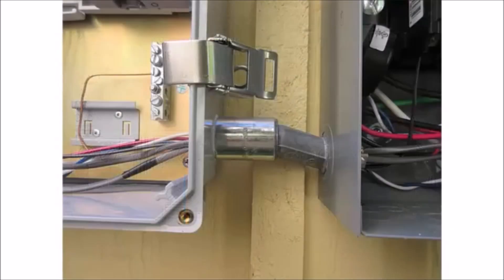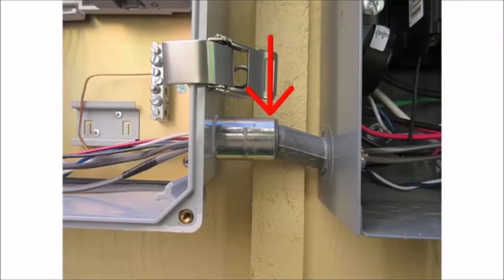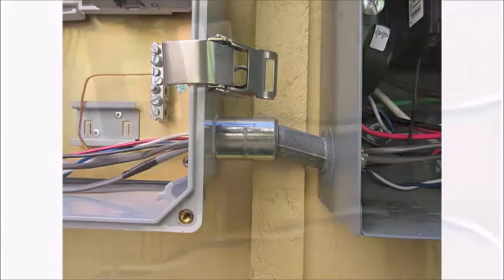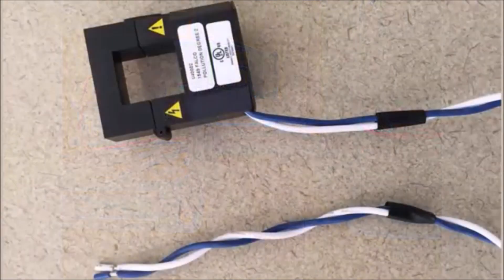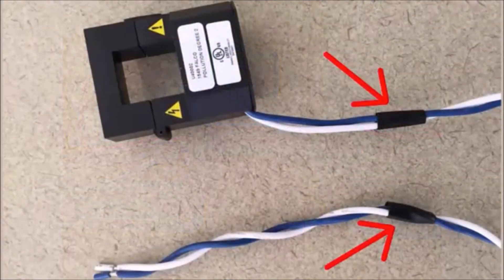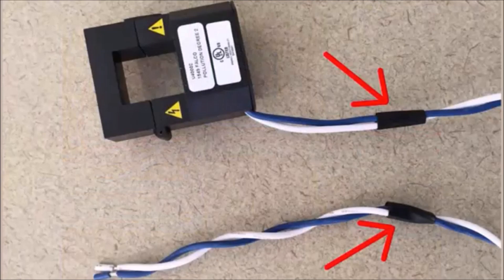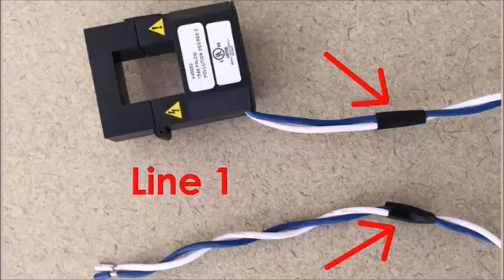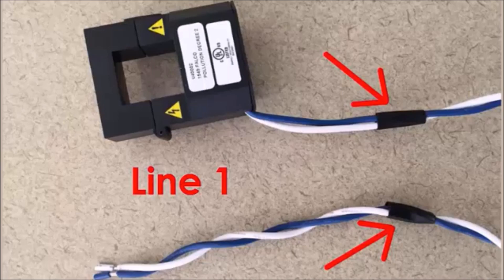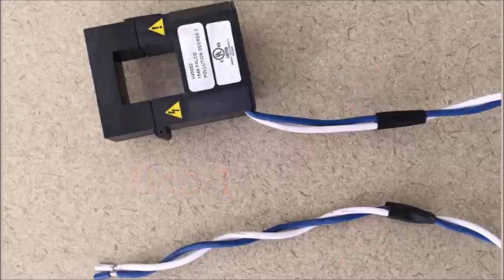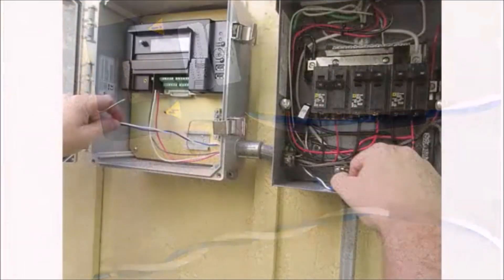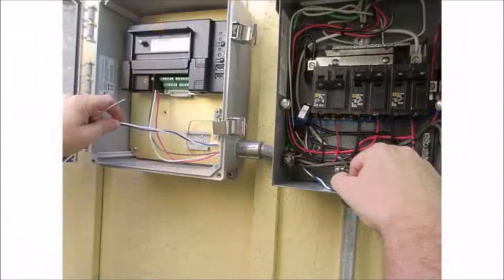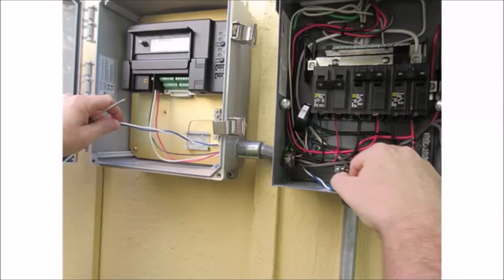Create a protected route using conduit for the CT wires from the main load center to the Envoy-S. Before running the CT wires through the conduit, use black tape to mark both ends of one of the CTs. You will use this for line 1. Marking the line 1 CT will enable you to correctly match both CTs for lines 1 and 2 between the Envoy-S and the main load center.